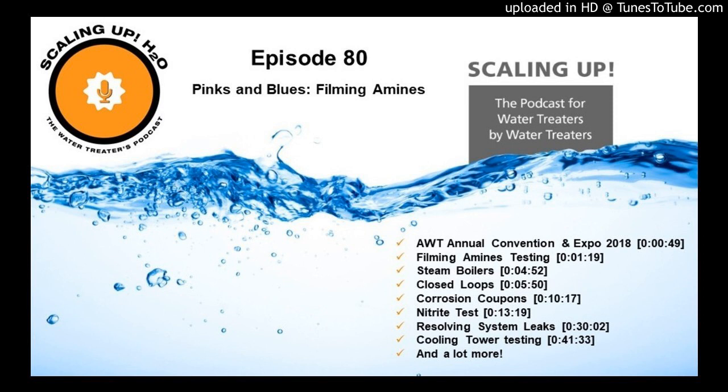Now, here's the key. Everything in that system has to be on, or you are not going to be able to measure that. So you need to work with your customer and make sure that they turn every single valve on every part of that system on, so it's getting good circulation. And you want that to circulate for about a day, and you already know that there's no leaks in the system. Of course, if you have leaks, you're going to have issues. You're not going to be able to do this.